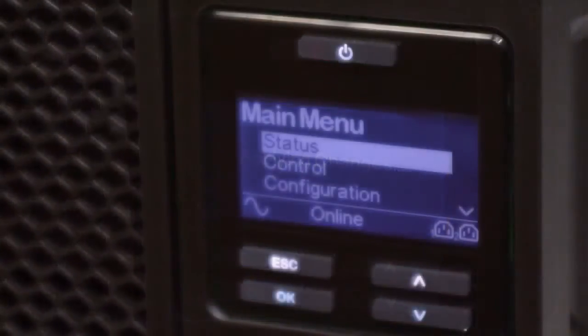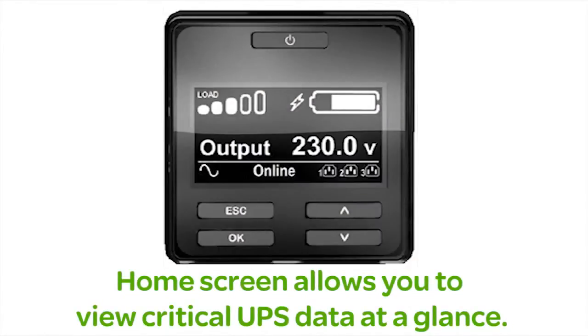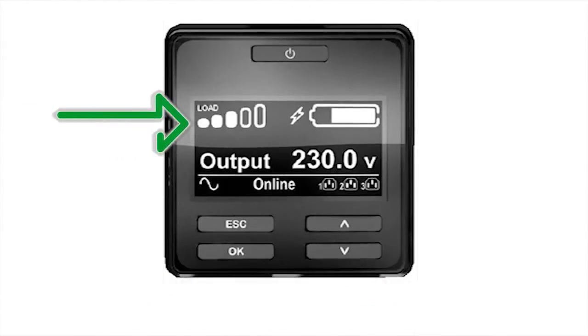Users can change any of the selected options once they've exited the setup wizard. The LCD status screen displays a wealth of valuable information. The load indicator displays present UPS load in relation to overall UPS capacity. The approximate load capacity percentage is indicated by the number of load bar sections illuminated.